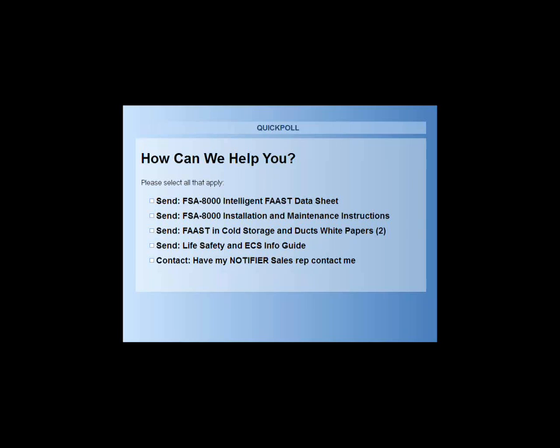Okay, all right. They're wondering about how blockage is detected. Is it based on the number of holes in the pipe that might be blocked, or how does the detector go about viewing blockage? Okay, so when you initially send the sensitivity configuration to the FAAST device, it's going to take the first 5 minutes after that configuration is received to set its airflow baseline. Basically, it's looking at the airflow coming in from the pipes through the FAAST detector, and it's going to say, okay, this is my normal airflow. This is what I expect to see.